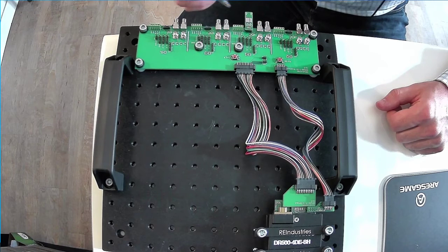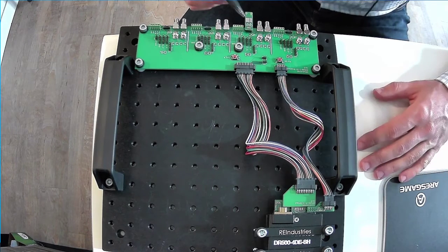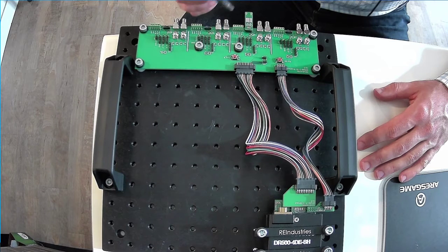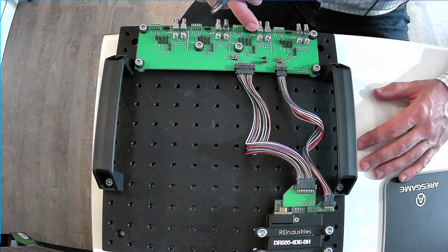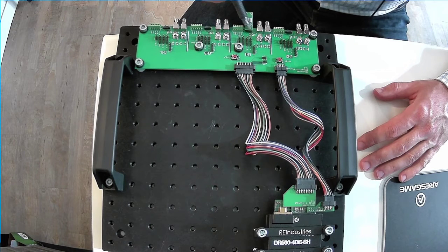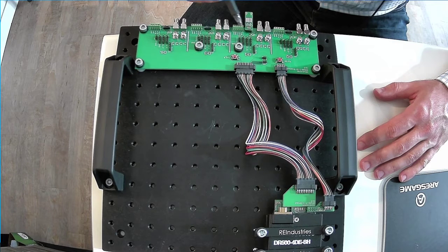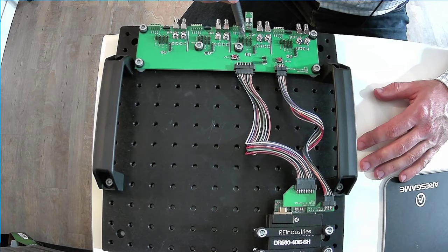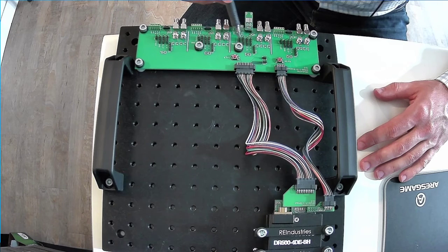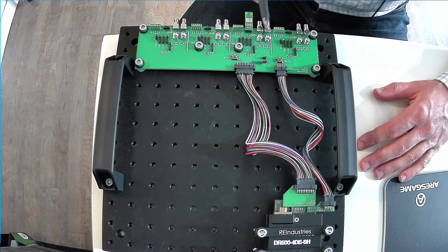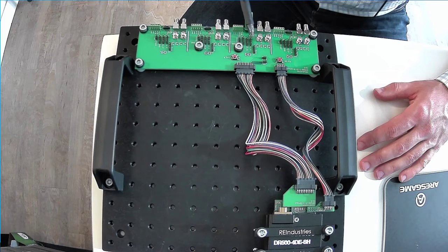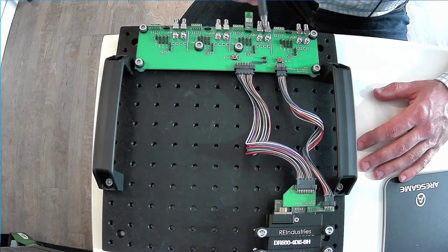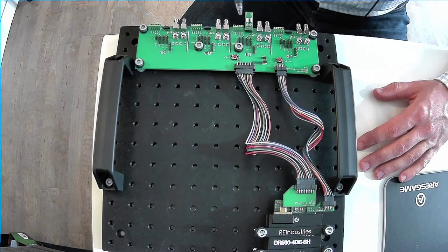And it also extends the life of the accelerometer cable harness so you don't have to solder it in somewhere, cut it out, and every time it's implemented, the cable harness length shrinks. So we've got that. There's a standard terminal block just for any kind of general use as well as rectangular headers here exposed for either signal input or signal monitoring. And so the four interfaces on each channel's input here are also all paralleled. So you can inject the signal into any one of these interfaces and monitor it from any one of these interfaces.